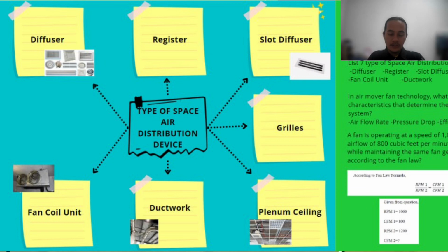First, diffuser. Devices that distribute air into the space in a controlled manner. They are typically mounted on walls, floor, or ceiling and are designed to direct flow and promote air mixing. Second, slot diffuser. A long strip shape with one or more narrow openings depending on the number of bars. Third, grills. These devices consist of a frame and fixed or adjustable parallel bars. Fourth, register. An air register is the same as a grill but with adjustable dampers in it.